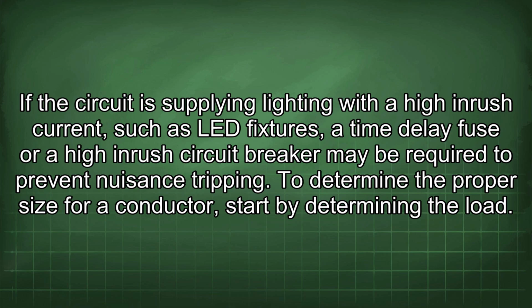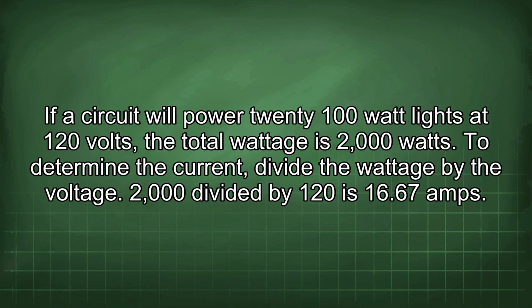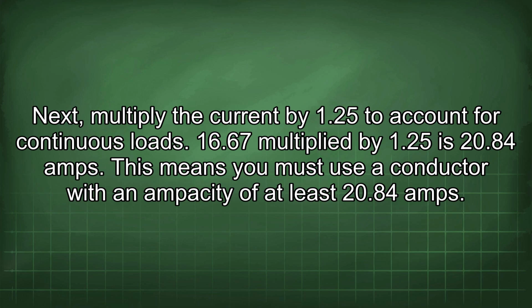To determine the proper size for a conductor, start by determining the load. If a circuit will power 20 100-watt lights at 120 volts, the total wattage is 2000 watts. To determine the current, divide the wattage by the voltage. 2000 divided by 120 is 16.67 amps. Next, multiply the current by 1.25 to account for continuous loads. 16.67 multiplied by 1.25 is 20.84 amps.